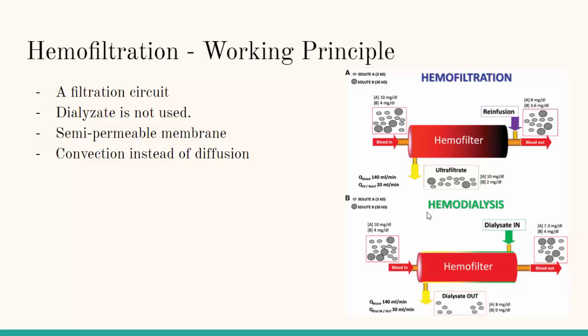Hemofiltration requires a large flow of water across a semi-permeable membrane. This water flow is induced by the blood with pressure gradient to the filtrate side of the membrane. The water flux drags the solute through the membrane. The selectivity of the process is determined only by the sieving properties of the membrane. Removing large amounts of plasma water from the patient requires replacement. Substitution fluids, a buffered electrolyte solution similar to the plasma water composition, can be applied before or after the filter.